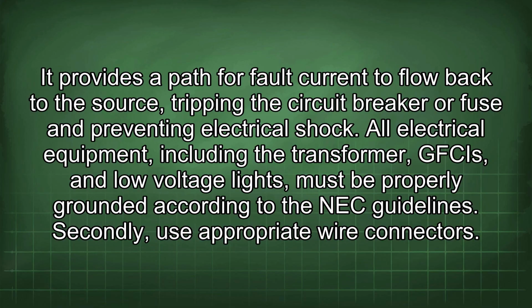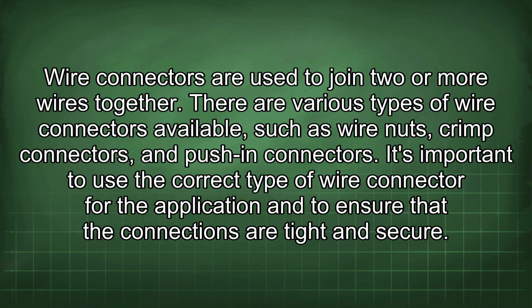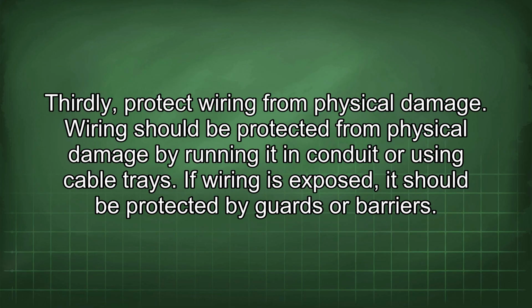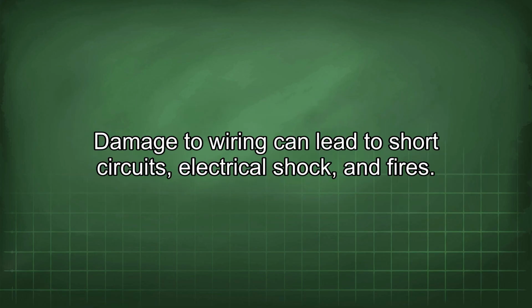Secondly, use appropriate wire connectors. Wire connectors are used to join two or more wires together. There are various types of wire connectors available, such as wire nuts, crimp connectors, and push-in connectors. It's important to use the correct type of wire connector for the application and to ensure that the connections are tight and secure. Thirdly, protect wiring from physical damage. Wiring should be protected from physical damage by running it in conduit or using cable trays. If wiring is exposed, it should be protected by guards or barriers. Damage to wiring can lead to short circuits, electrical shock, and fires.